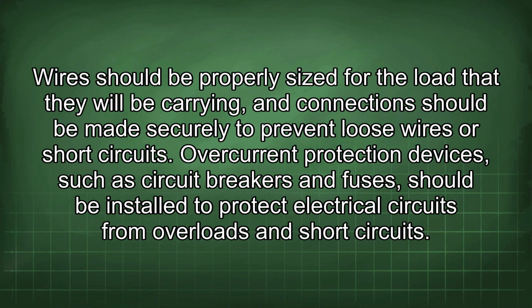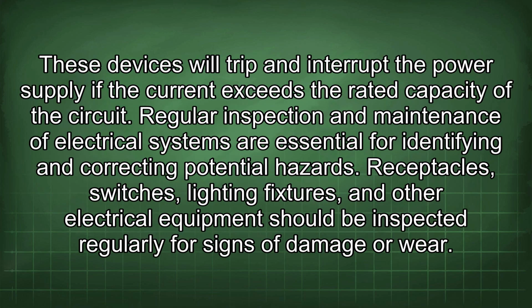Wires should be properly sized for the load that they will be carrying, and connections should be made securely to prevent loose wires or short circuits. Overcurrent protection devices, such as circuit breakers and fuses, should be installed to protect electrical circuits from overloads and short circuits. These devices will trip and interrupt the power supply if the current exceeds the rated capacity of the circuit.